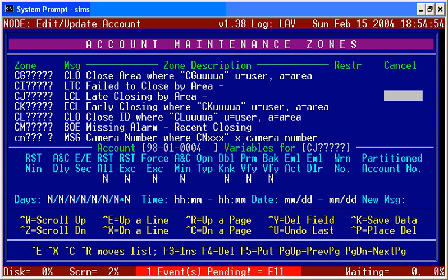Limit yourself to only identifying what zones are necessary in the base account, or only those redirections in the base account that are necessary. Let's just say if we had no redirections involved, we had 8 zones in the panel that we installed, I would imagine that I would only have 8 zones identified in my base account. I would have my zone account identified to pick up anything else that I perhaps might have missed.